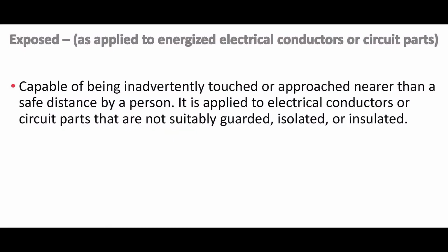So, exposed. It's important to understand exposed, because it's as important to know when we can work around electricity as to know when we can't. Otherwise we're all frozen with fear and can't work on anything, and we've got to be able to work on things. Understanding that the shock hazard only exists when conductors are exposed is important. This outlet has a cover on it, so there's no shock hazard with this outlet because it's not exposed.